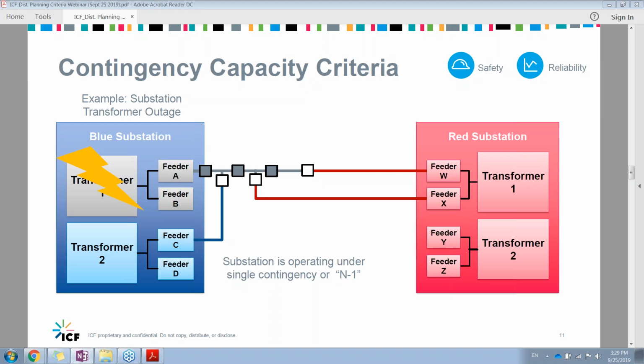This is where the planning criteria for a single contingency, also referred to as N-1, comes into play, where these adjacent feeders, C, W, and X, were designed to be able to pick up a portion of feeder A and restore service. Let's look at the next slide, please.